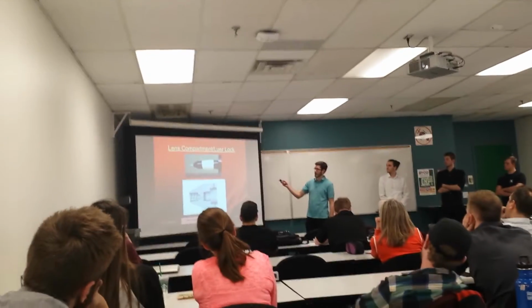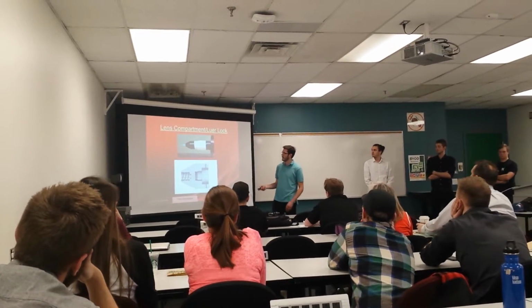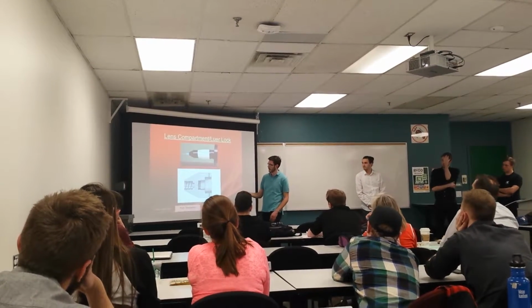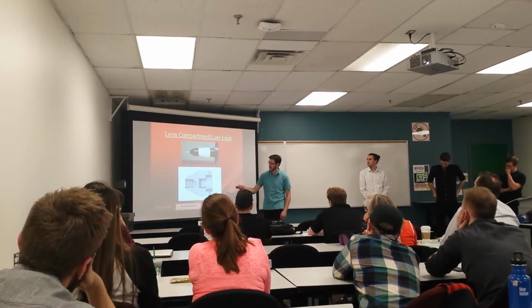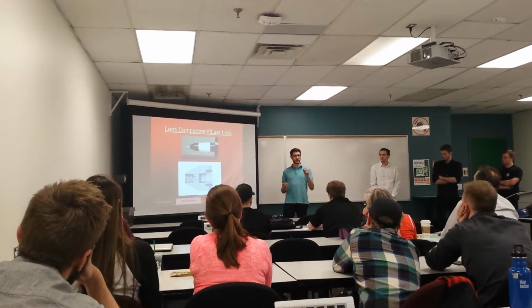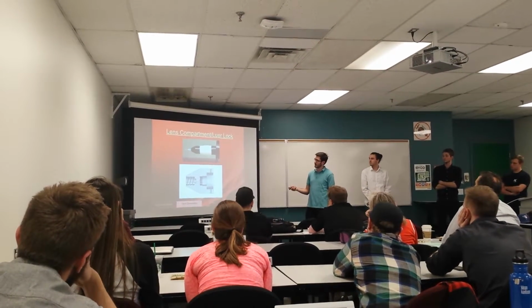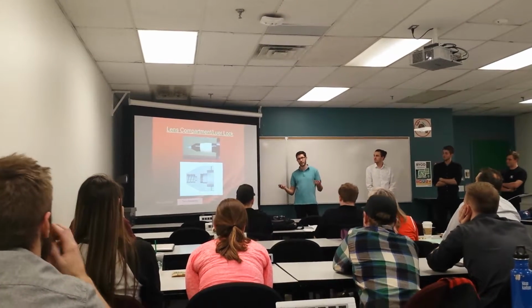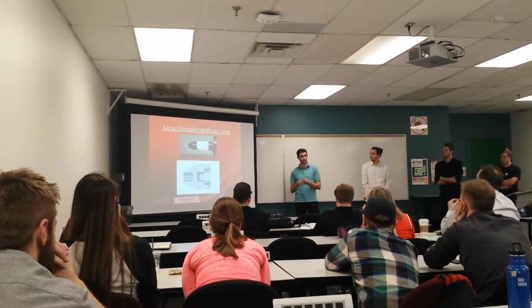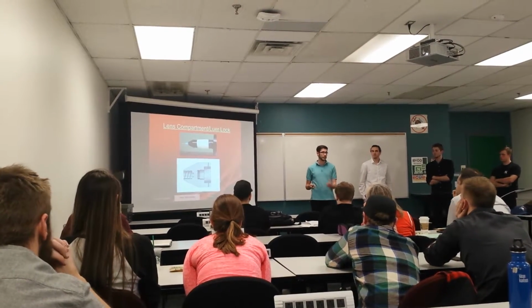We had the lens compartment lock. Here, this part is where it attaches to the previous component we just spoke about. Then the aspheric lens would be tightened through this threading, and the distance between this line here and the actual hole where the needle would go had to be that 18.4 millimeter distance to ensure that the focal point, where the diameter is smallest, would actually enter inside the needle. This little hole here would be where the next component would attach, the final part locating the actual needle to the piece. And then there was the threading, which was the fastening mechanism for the needle.